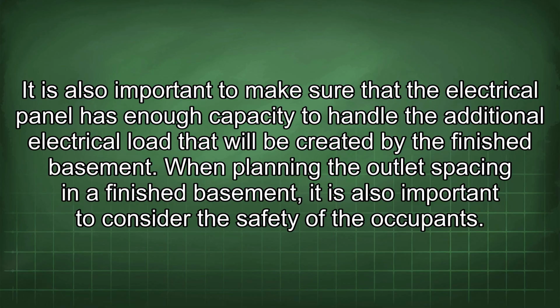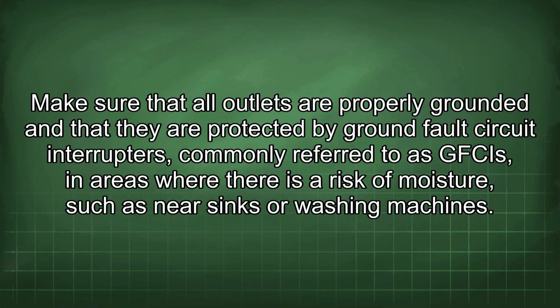When planning the outlet spacing in a finished basement, it is also important to consider the safety of the occupants. Make sure that all outlets are properly grounded and that they are protected by ground fault circuit interrupters, commonly referred to as GFCIs, in areas where there is a risk of moisture, such as near sinks or washing machines.